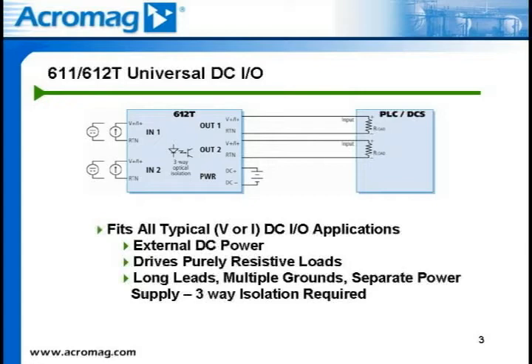The ground potential at the field sensor is also likely to be different from the power source and the PLC. Therefore, input to output isolation is also necessary. By installing the 611T or 612T isolator, the three-way isolation eliminates the potential for ground loops or floating signals.